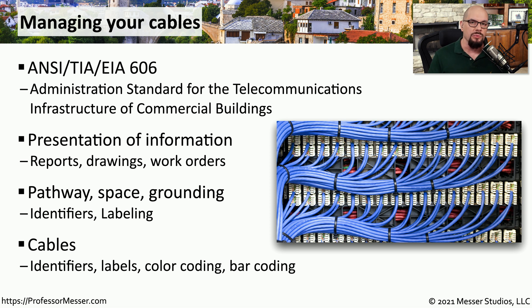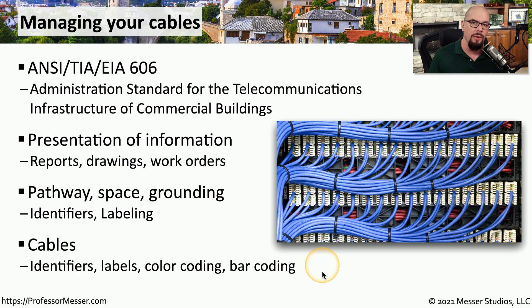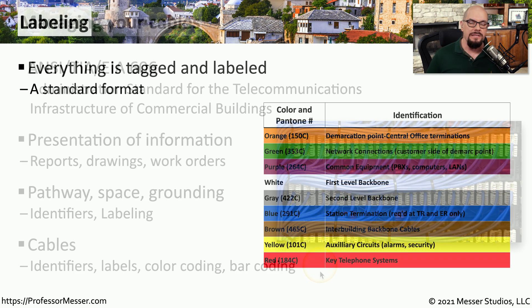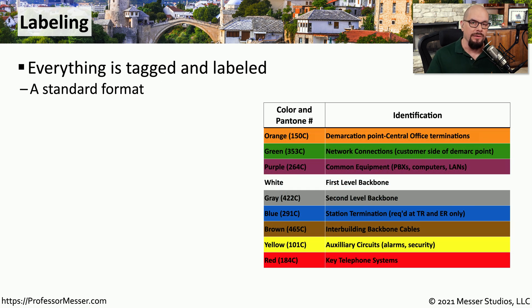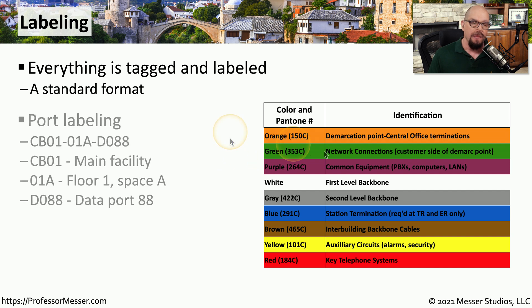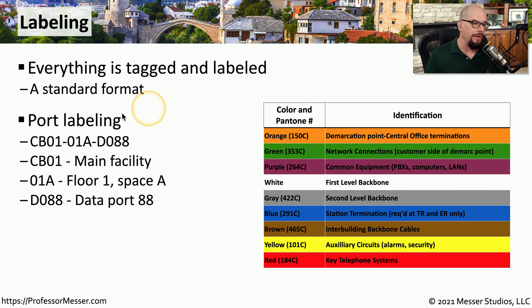Having labels on these cables can be critical, because when problems occur, it's important to know where both ends of that cable may be. So you need to make sure you have identifiers, labels, or perhaps even color coding or bar coding. The 606 standard can help quite a bit with understanding the best way to label and how you can keep that labeling consistent between locations. For example, each of your facilities may be labeled in a very specific way — a label may show CB01, 01A, D088.